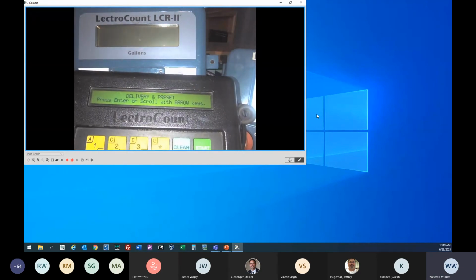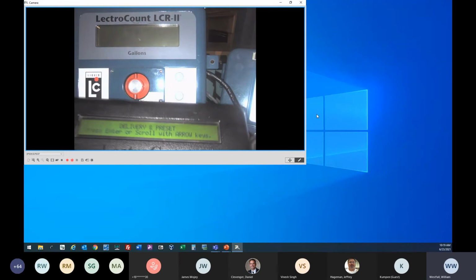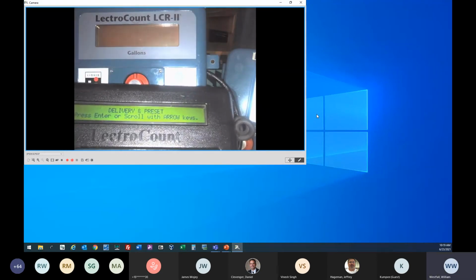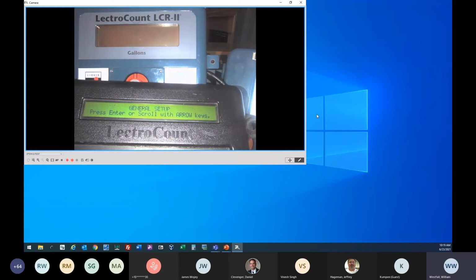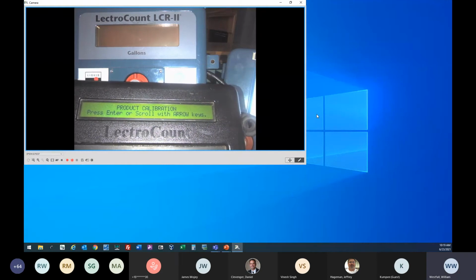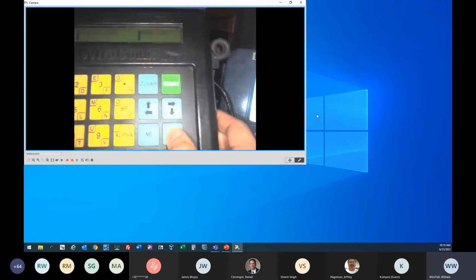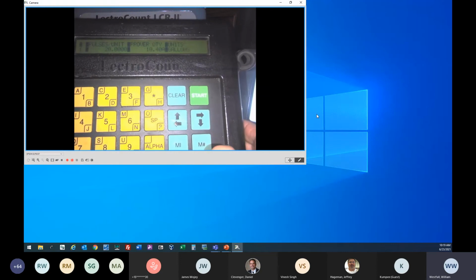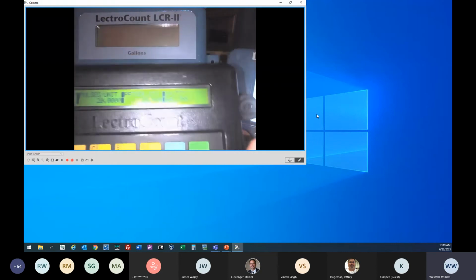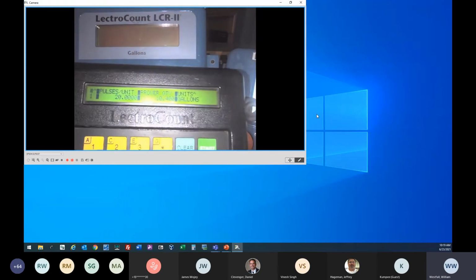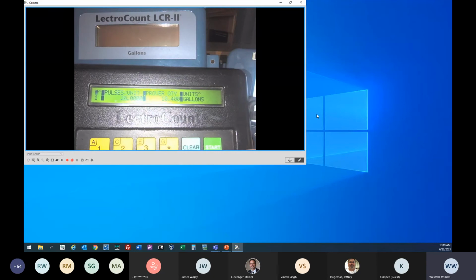So what we want to do is, we're in calibration now. The red knob is straight down. We want to scroll over until we see product calibration. So we're in product calibration. We go ahead and hit the enter key. Hit the M/I key, right here. That'll get us to the next one, and the next one. Here's our prover quantity. So this is really where we want to be throughout this whole process.